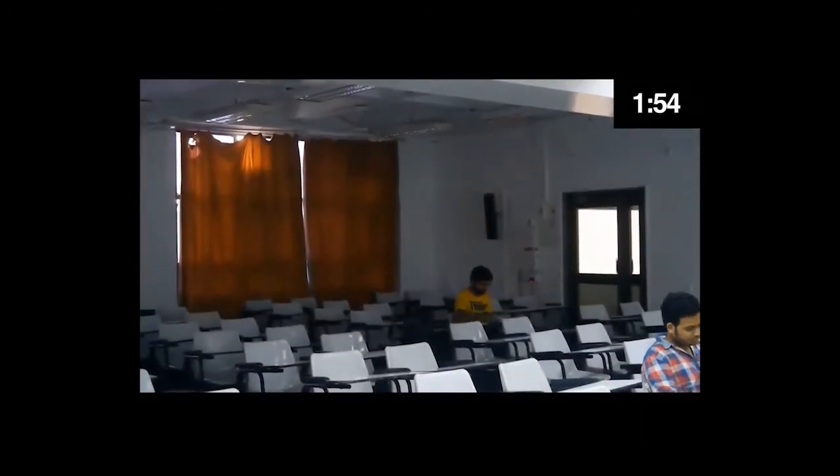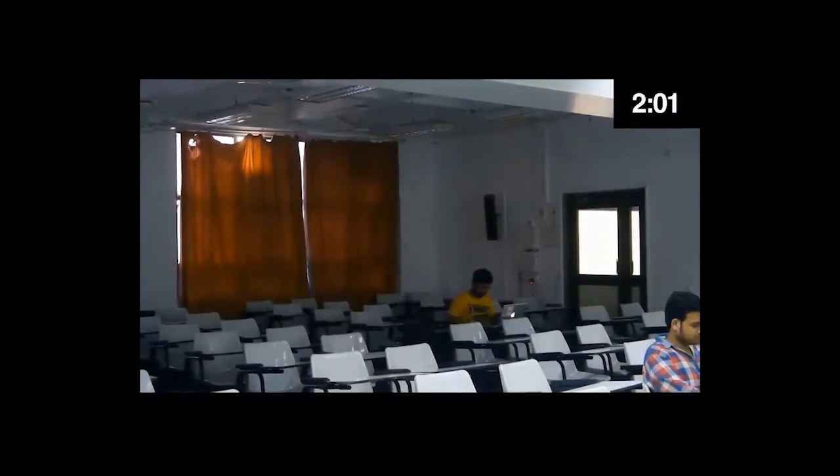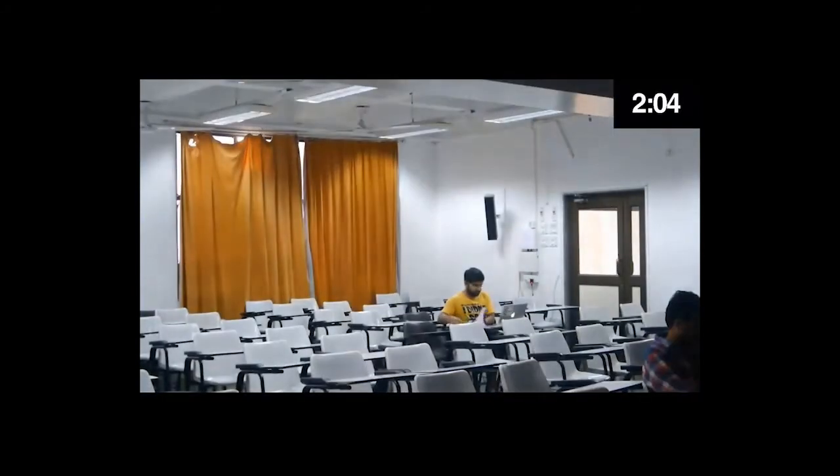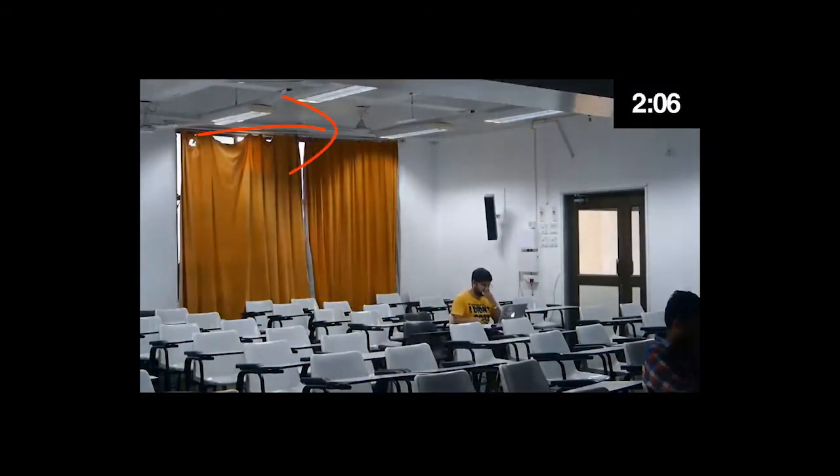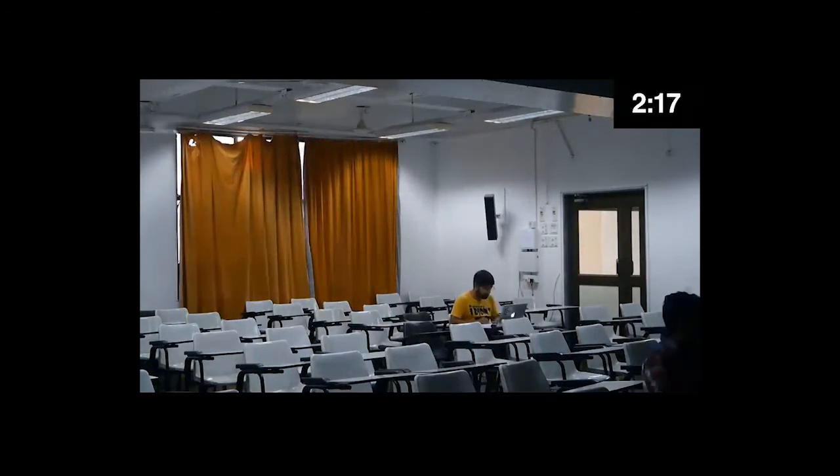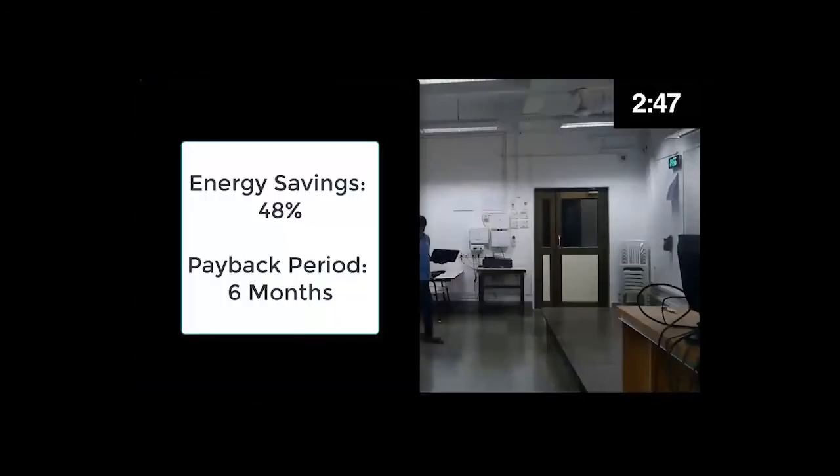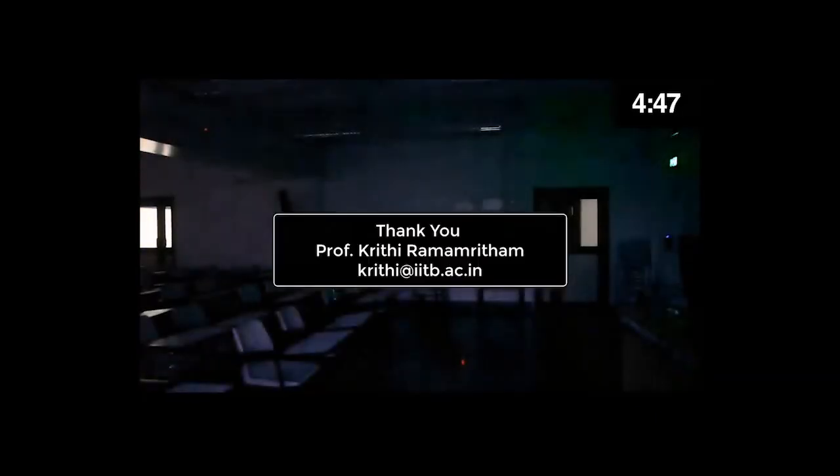The appliances in this zone are turned off since the zone was previously unoccupied. We turn off appliances in unoccupied zones, thereby reducing power consumption per room. If occupancy continues to be detected for a certain period of time, appliances turn on. We have calculated the energy savings of the smart classroom complex to be 48% with a payback period of 6 months, which is very attractive. When the system fails to detect human presence for 30 seconds, it infers a state of zero occupancy and turns off all appliances. Thank you for watching.